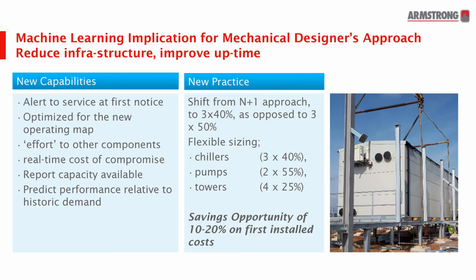Getting back to the cost of a chiller plant and the implications this has: when we design cooling systems for data centers, we're very concerned about resilience, uptime, and availability. This is a key criteria for every data center. One reason we're so concerned, and go to N+1 and 2N designs, is that we're unable to predict how much capacity we actually have from our cooling system.